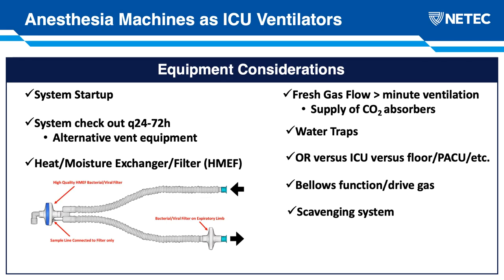From an equipment perspective, we talked a little bit about system startup. We want to make sure that someone is there who is familiar with the equipment. We typically, when thinking about an ICU use, would remove our anesthetic vaporizers. And similarly, those machines need to be flushed to ensure there's no residual anesthesia gas within the internal components. There's a very small percentage of the population that is susceptible to a condition known as malignant hyperthermia, and we wouldn't want to inadvertently trigger that in any of our patients being placed on long-term ventilation.